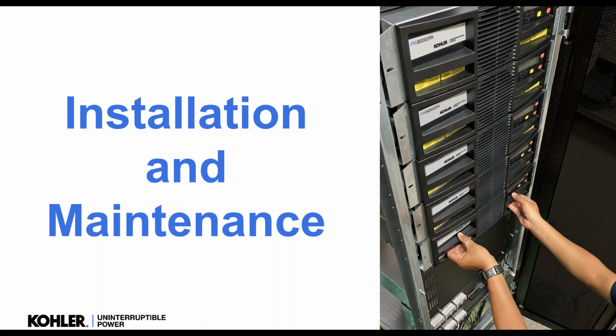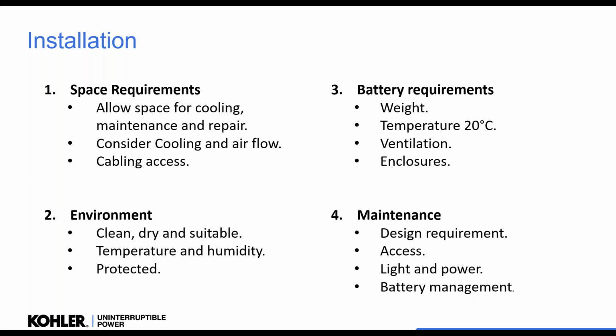Okay, so we've got to look at installation and maintenance, and this is something that unfortunately for life safety systems isn't always done well, and it is important that we try. We must put it in the required space. Most companies will give guidance on how much space is needed for cooling, for maintenance, and repair. That has to be considered. We need to make sure it's cooled, has adequate airflow, and we can get the cables in and out.